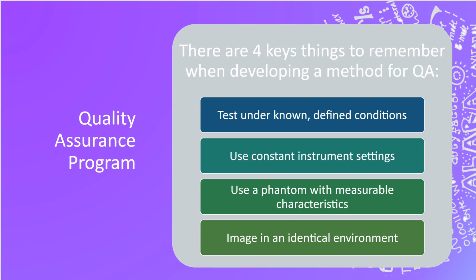We also want to use constant instrument settings, so it's unhelpful if we do all of our QA using the adult echo setting on our machine, and then the next time we decide to do first trimester OB with a different transducer. That doesn't help us. That doesn't tell us has anything changed from the first time to the next time that we do the quality assurance. So we want to use constant instrument settings.